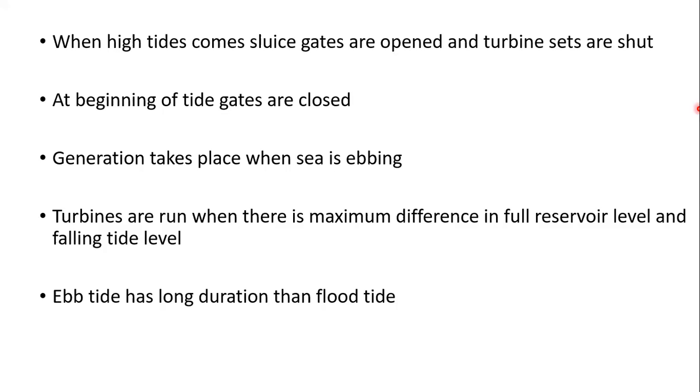As long as the period of generation of power, at the beginning and finishing of the work, we are having minimum operating head only. Adjustable blade bulb turbines are used specially for these arrangements, for these operations. These are used under low and variable heads also.